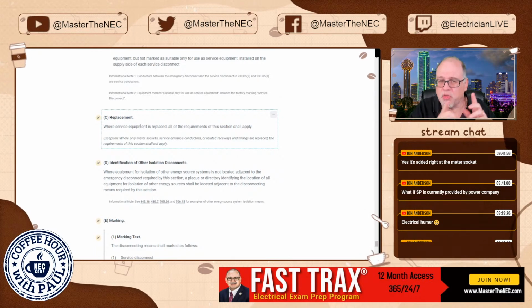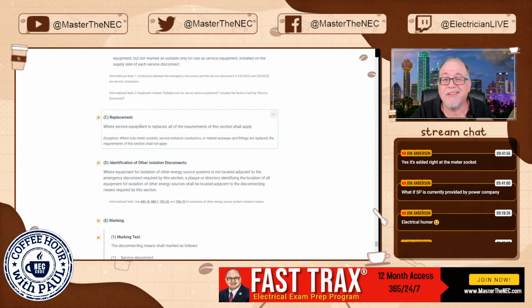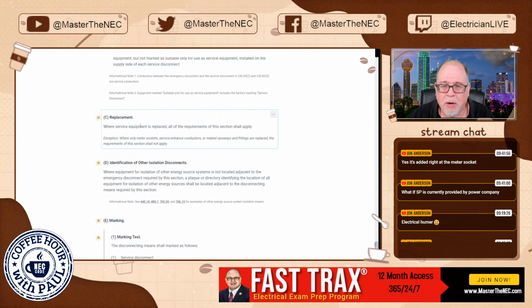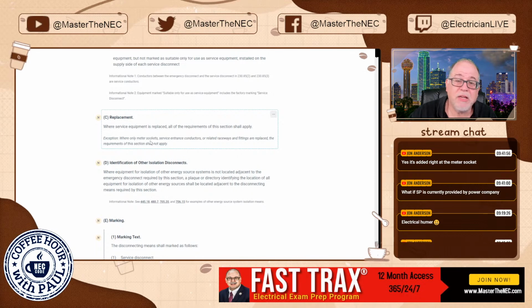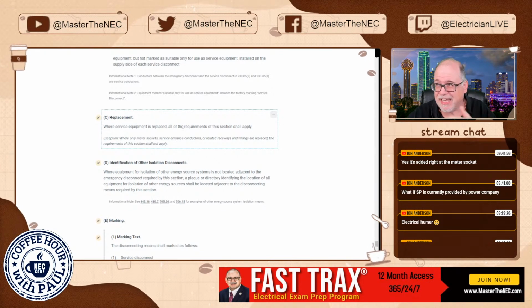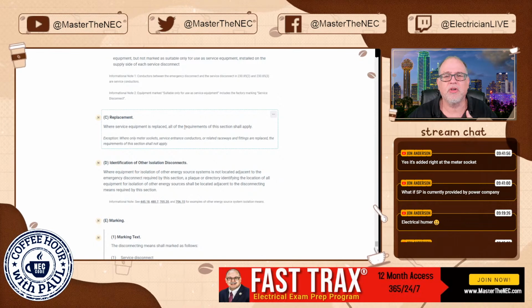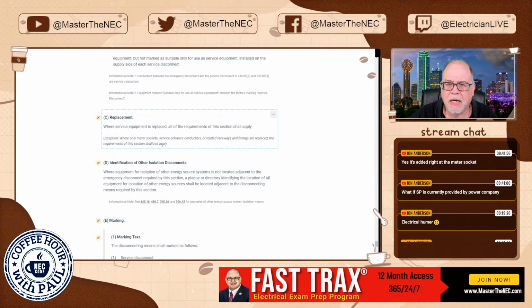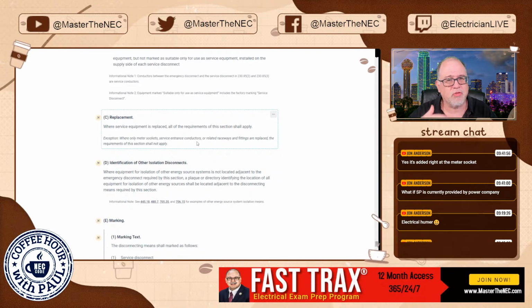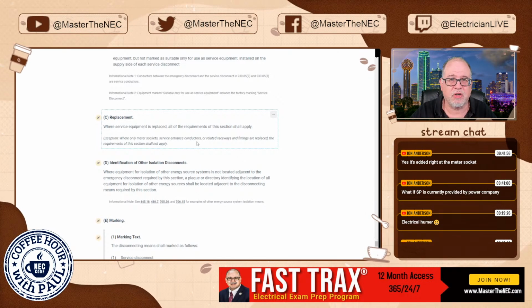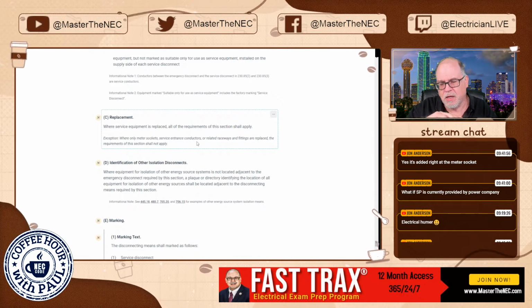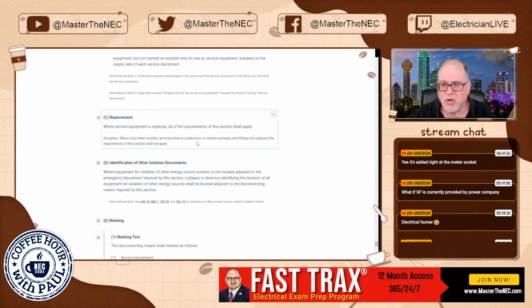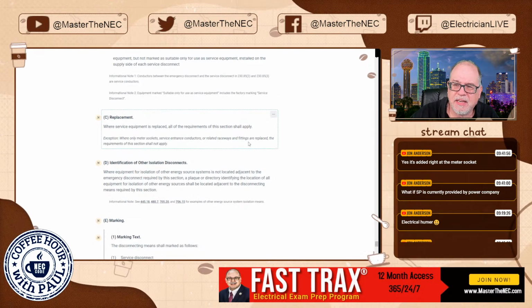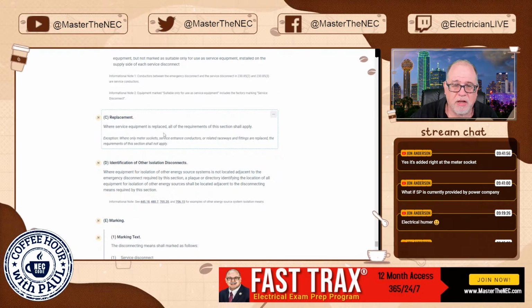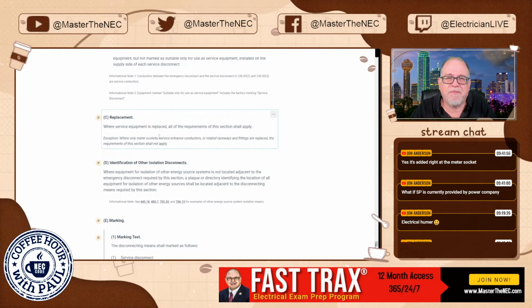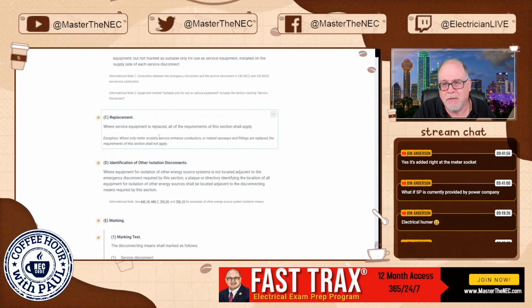And remember, the surge protection device rule also applies because that is all kind of a replacement rule. Now, what is the exception? It says we're only replacing meter sockets, maybe because of a storm, like Storm Ian that came through, and all you're doing is replacing the meter socket for damage. Service entrance conductors, maybe you're just replacing damaged service entrance conductors, or maybe it's SE cables that have been weathered and worn or damaged. If you're just doing that, or related raceway and fittings are replaced, the requirements of this section shall not apply. Okay, you're just kind of fixing something that is a safety concern, right?